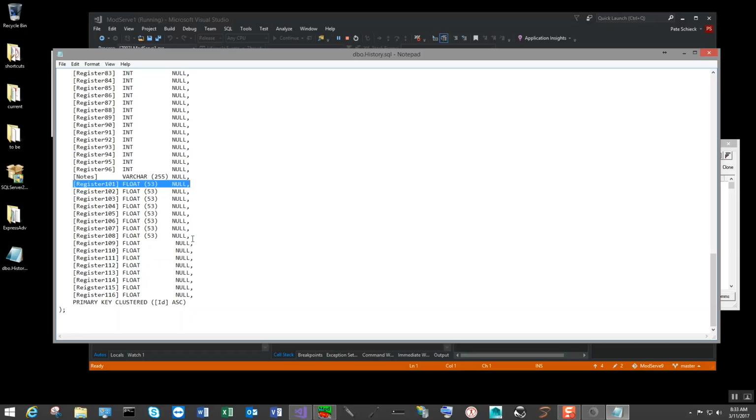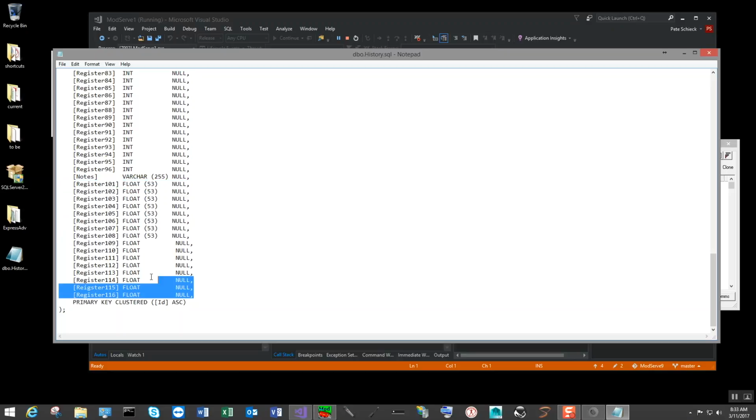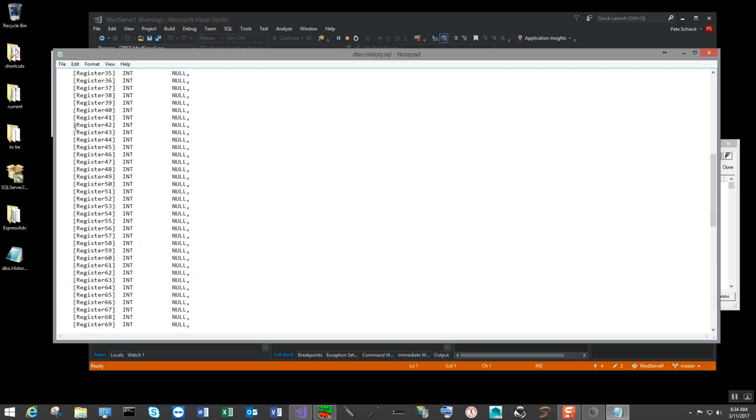So you've got these registers, which can show analog data: temperature, flow, how fast a fan's going. And you've got some 64-bit ones as well for higher-end usage, such as GPS coordinates or anything else you're using the controller to do. I wanted to make sure there was still a base pack of four or so registers that could be cleanly output to any HMI, touchscreen, Excel file, whatever, and you can see the final value. Because when you're looking at Modbus registers and you're just looking at registers 43 and 44, you're definitely not converting that in your head to IEEE 754.